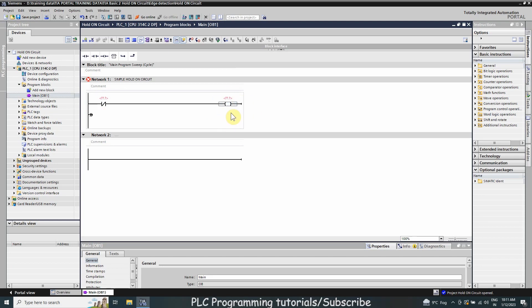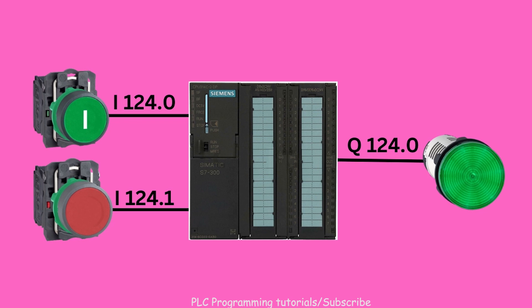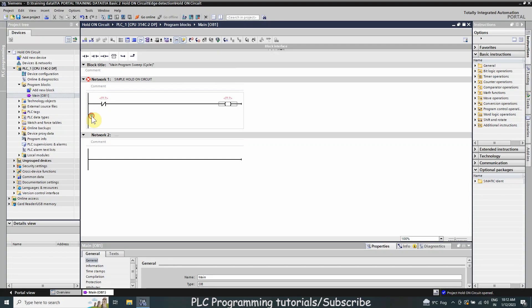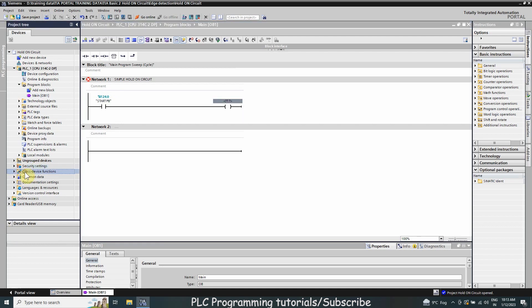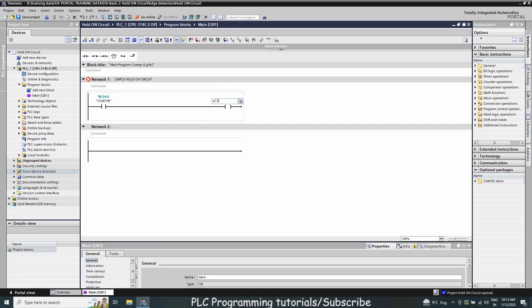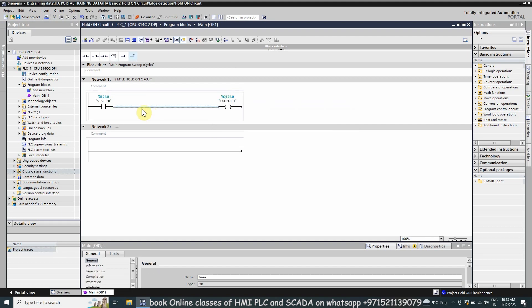For today's tutorial, we have connected two push buttons at inputs I124.0 and I124.1 of the PLC, and one output LED is connected at Q124.0. We are going to use normal open and normal closed contacts to make a simple hold-on logic. First we will insert a normal open contact of I124.0 — our start push button — and assign the output coil as Q124.0.